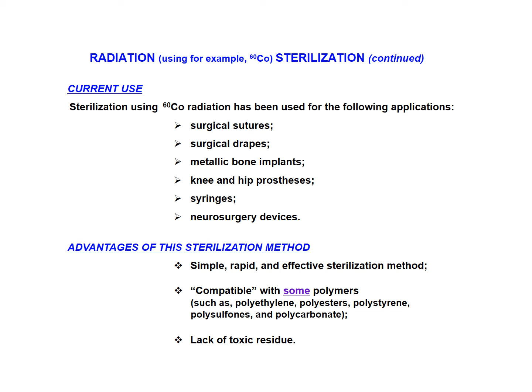And as biomaterials engineers, we must be aware of the polymers which are not compatible with this method. Another advantage of radiation as a sterilization method is the fact that it doesn't leave any toxic residue. As with the other two sterilization methods discussed, radiation has certain disadvantages. First and foremost is the high cost required for building a special facility, installing the isotope and running that facility for sterilization purposes.